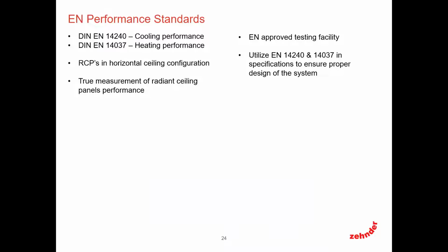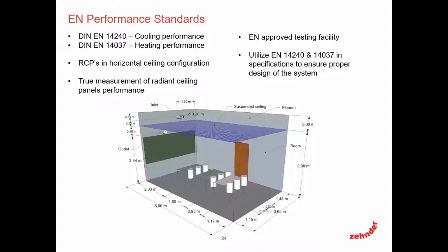So over about 15 years ago, the industry came together and said, enough is enough. We need to develop standards that create a benchmark and standard for everybody, all radiant manufacturers. And we developed two standards, one for heating and one for cooling. And these standards clearly define not only the lab, but where the globe sensors go, how the panels are installed, the active area, the mounting heights. Every parameter is defined in these standards to make sure that when you compare performance from one manufacturer to another as a designer, you're comparing apples to apples, and you're not getting, quote unquote, in-house testing or tested in accordance with. This creates that benchmark, and it's similar to AHRI when you test coils or other mechanical equipment.